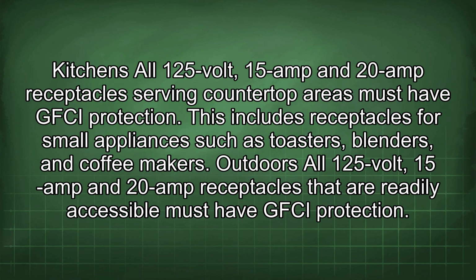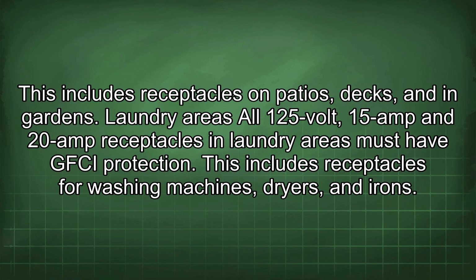Kitchens. All 125 volt, 15 amp and 20 amp receptacles serving countertop areas must have GFCI protection. This includes receptacles for small appliances such as toasters, blenders, and coffee makers. Outdoors. All 125 volt, 15 amp and 20 amp receptacles that are readily accessible must have GFCI protection. This includes receptacles on patios, decks, and in gardens.